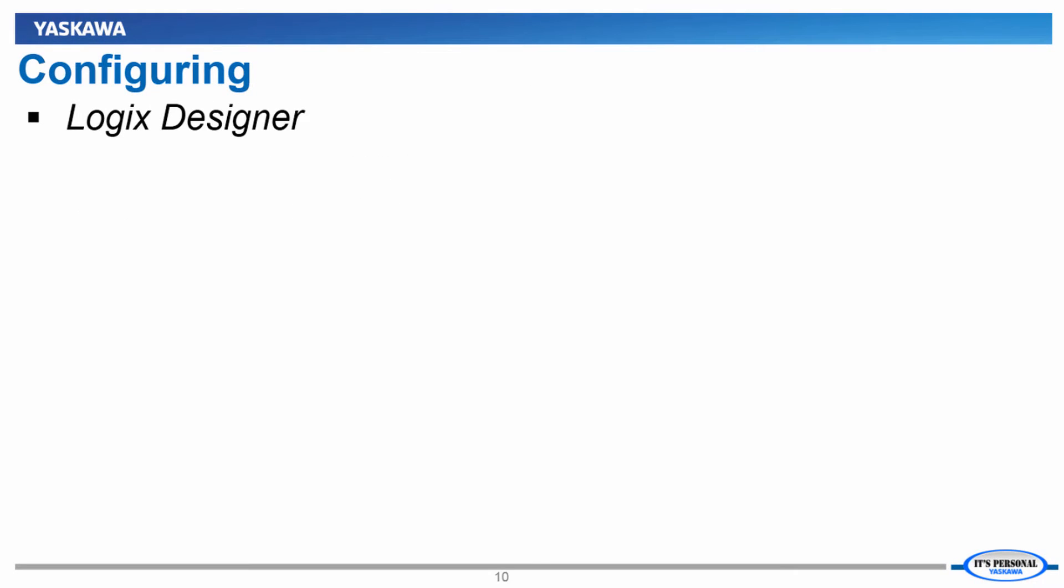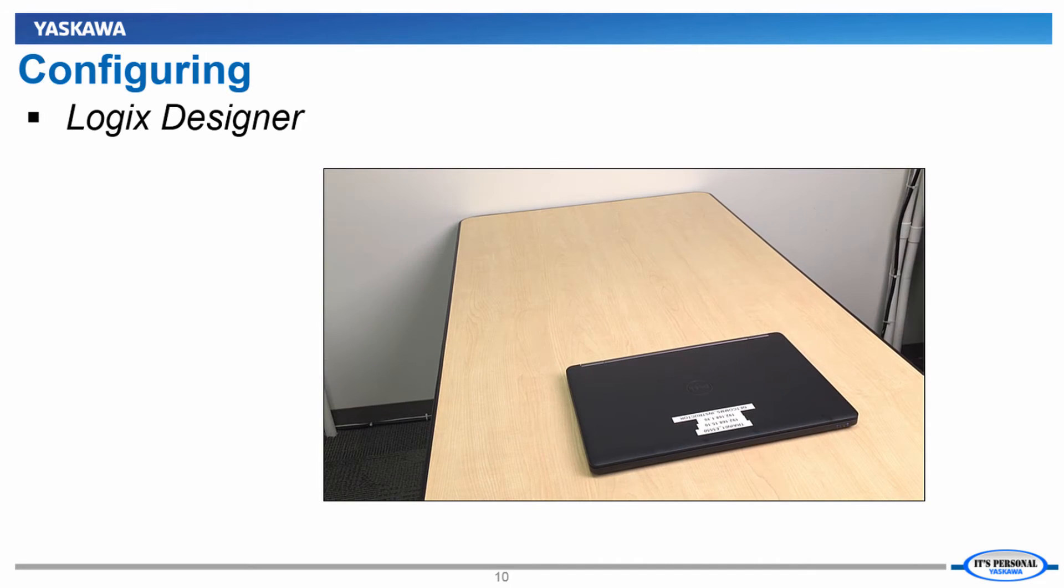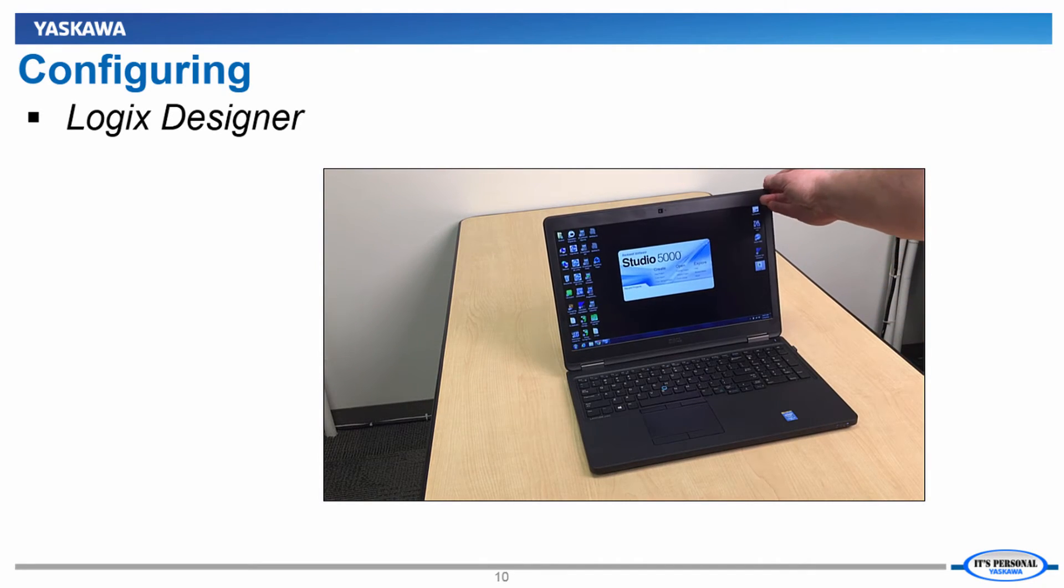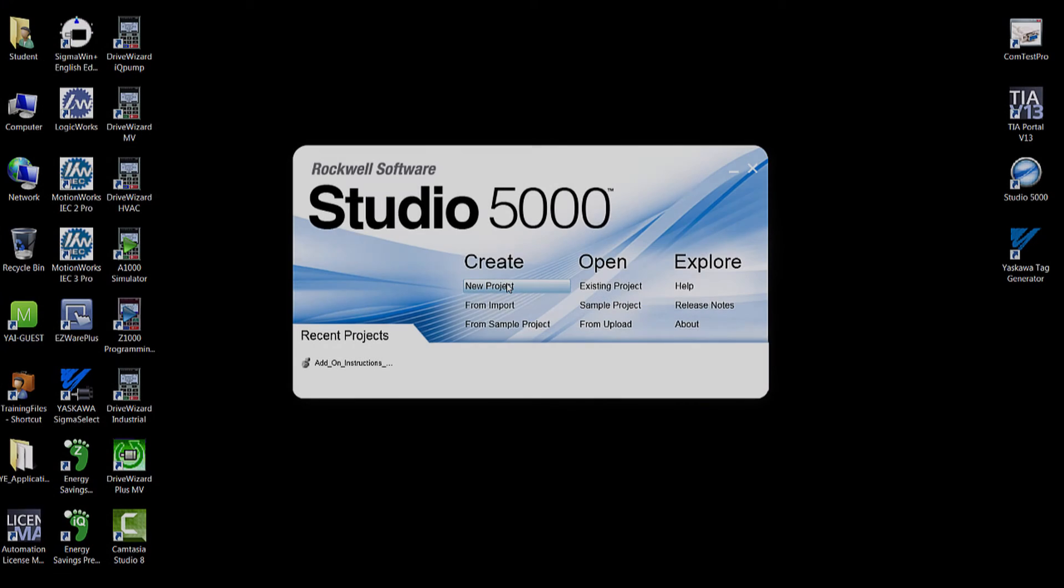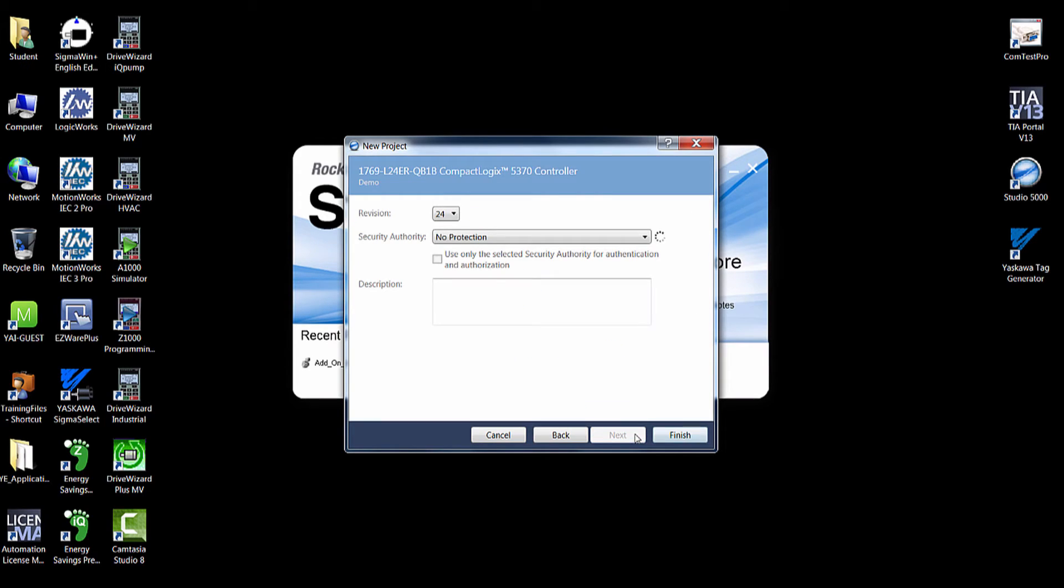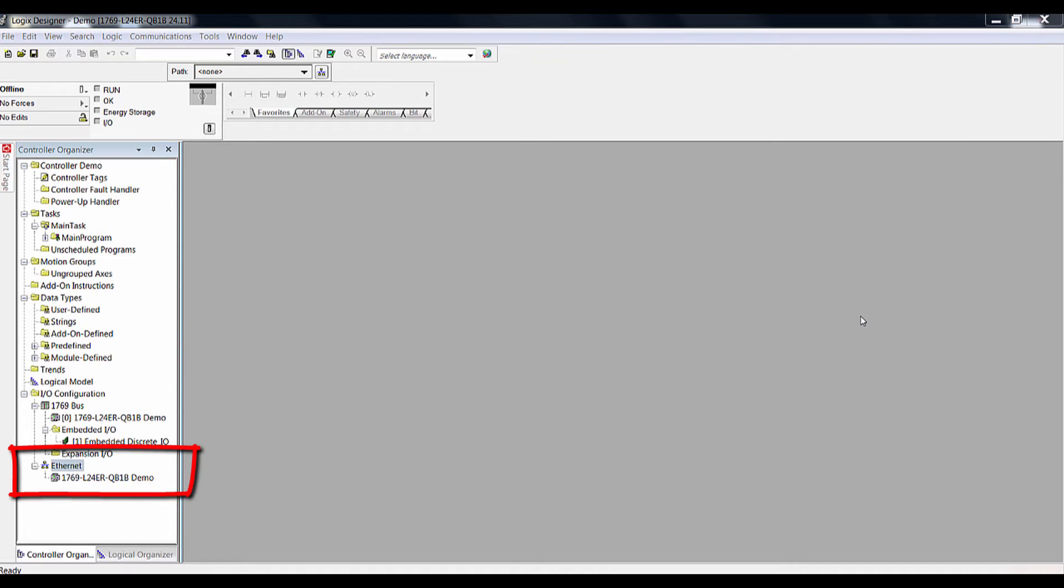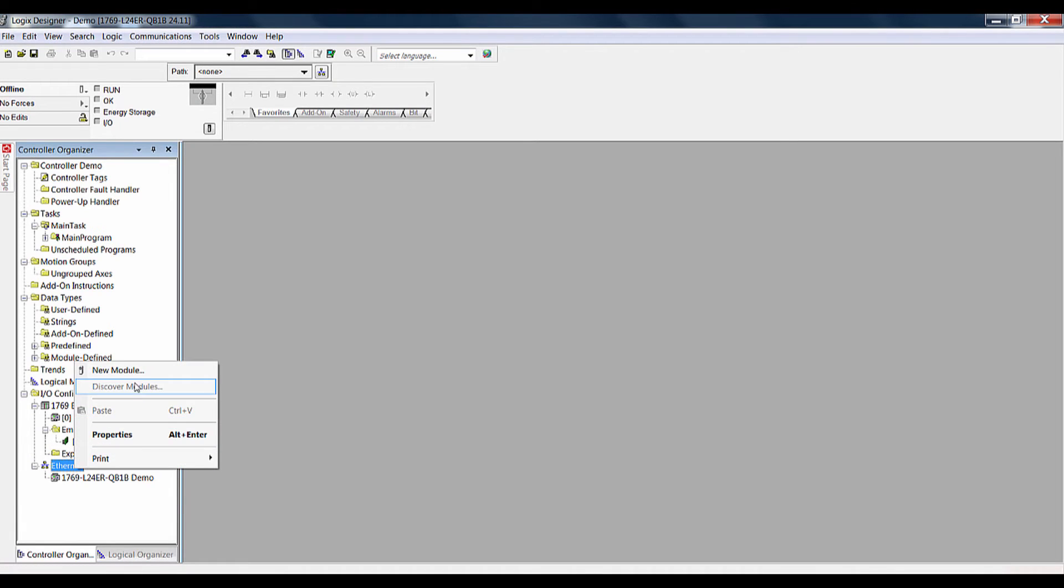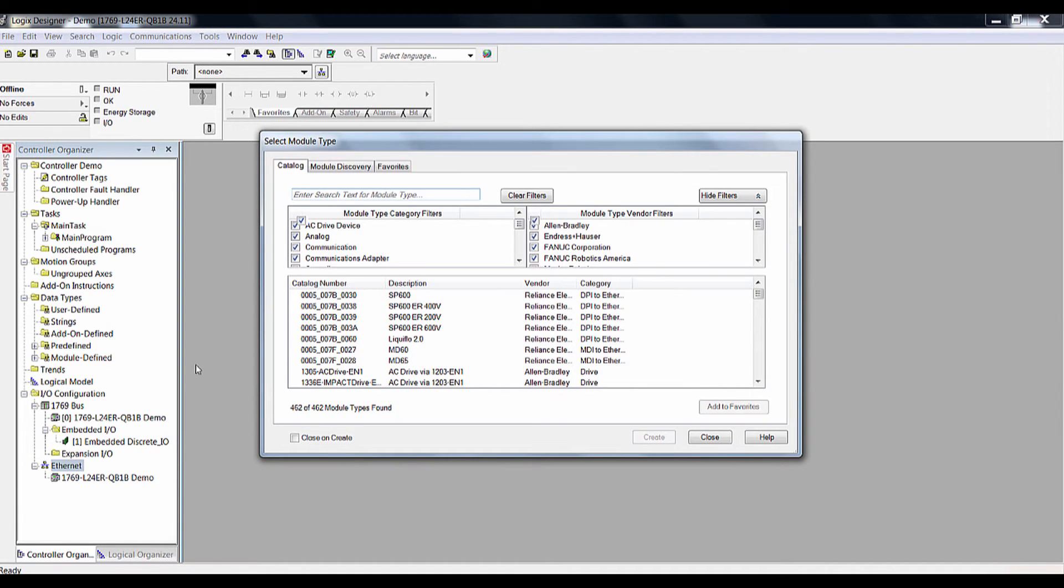Now let's move on to configuring the PLC so that it can start communicating to the VFD. To do this, we'll need to use our Logix Designer software. We're going to assume that you have a project started and that your PLC is configured minus the VFD. Find the Ethernet icon under the controller organizer on the left side. Right click on that icon and select New Module. It will bring up a list of devices that can be added to the PLC.